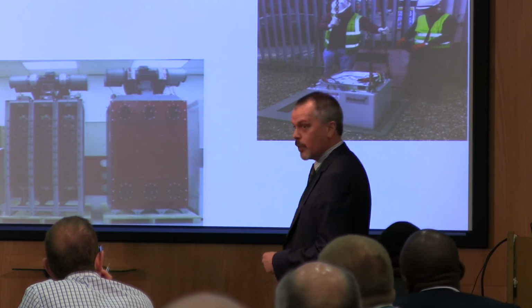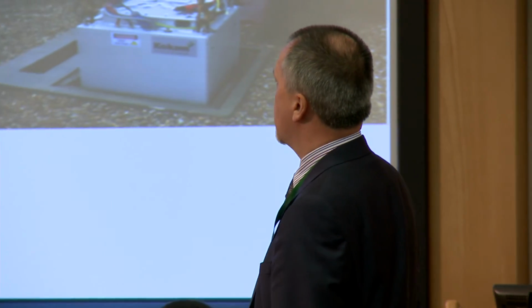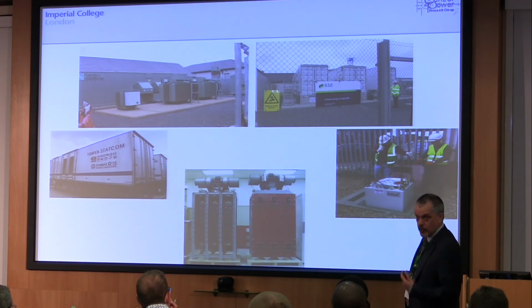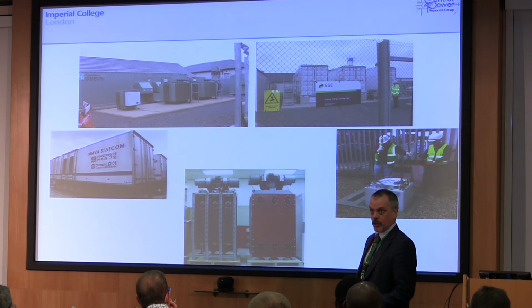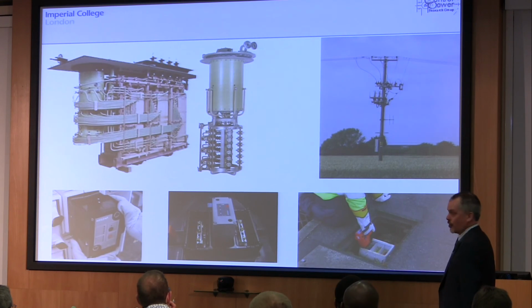Perhaps one place where it is well established is in static transfer switches, and that's this bottom picture here, where you want to do very rapid changeover between supplies on a critical load, then a semiconductor means to do that is compelling. But mostly, if you look at how distribution networks are controlled, it's very traditional equipment.